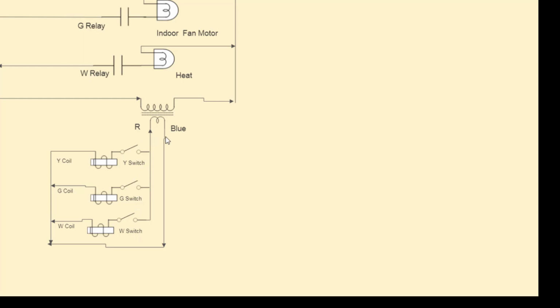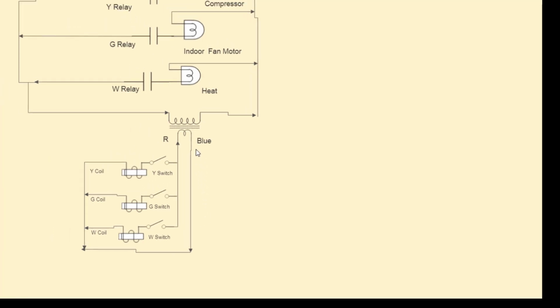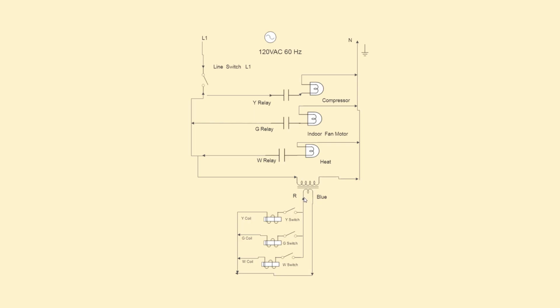The R and the blue. The R is your red wire. It's what we use in low voltage as your hot wire. And your blue is your return wire. So you see on the other side of the coil, all of these get connected to that blue wire, and it comes back around and goes right to that return on that step-down transformer. And all of our wires come from the hot wire of the transformer here. You have power waiting to go through this coil, and power waiting to go through this G coil, and power waiting for you to close that W switch so it can go through that.